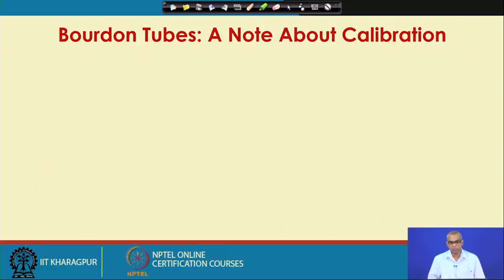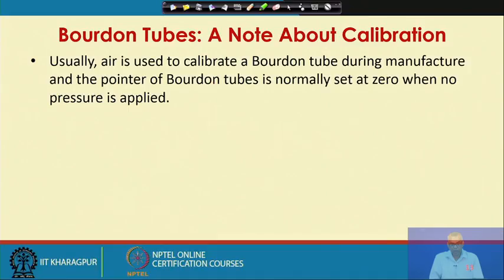Finally, we talk about something on calibration of the Bourdon tube. A Bourdon tube can be calibrated using the dead weight pressure gauges that we have talked about. We have talked about the procedure, so, following the procedure, you can calibrate a Bourdon tube. Usually, air is used to calibrate a Bourdon tube during manufacture, and the pointer is normally set at 0 when no pressure is applied.